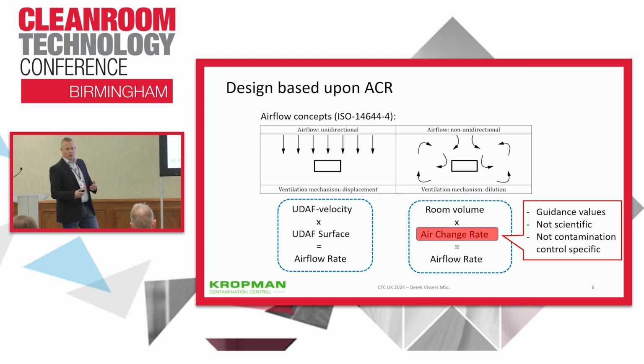As mentioned multiple times in the earlier presentations, the air change rates are guidance values or rule of thumb values. They are not scientific and not contamination control specific at all. So it does not take into account the actual process in your clean room or the amount of operators or the clean room garment. It's just a rule of thumb value.